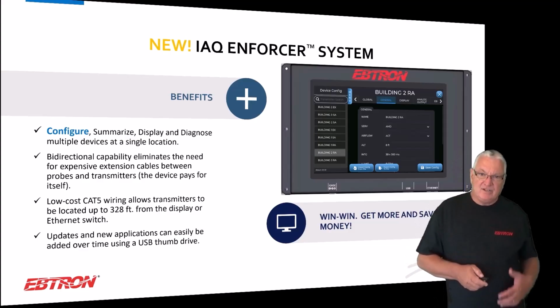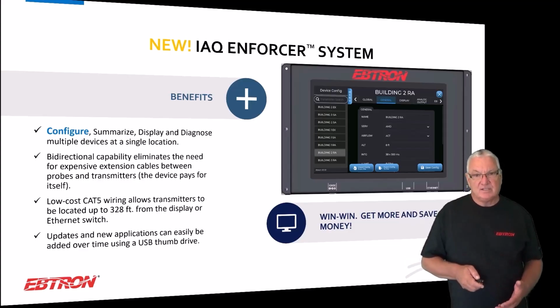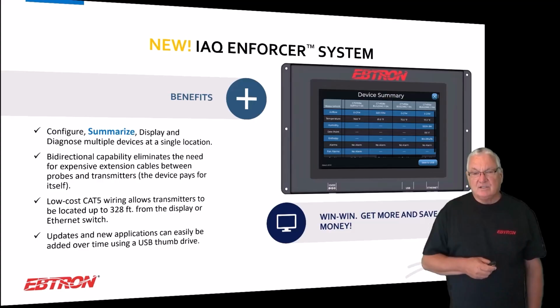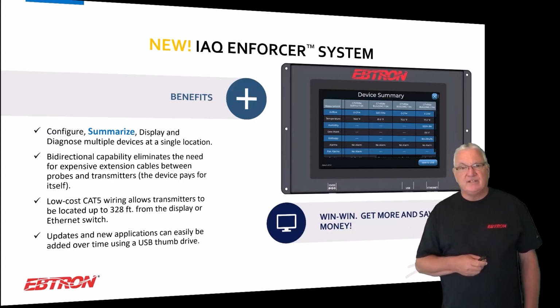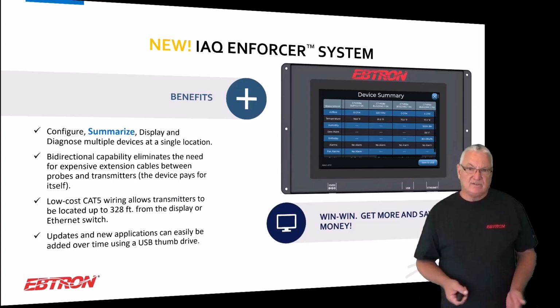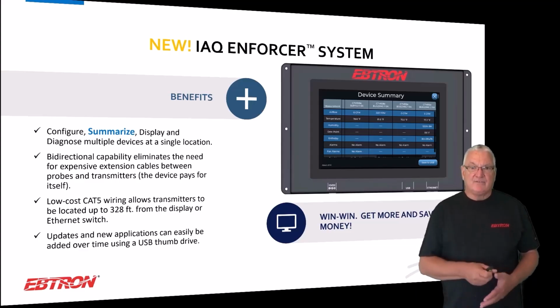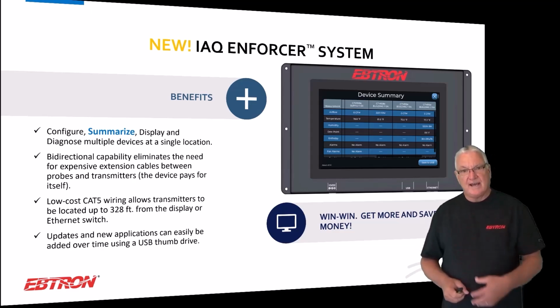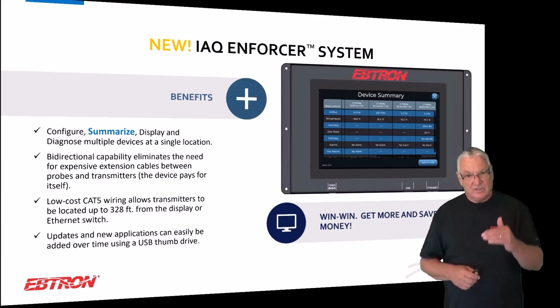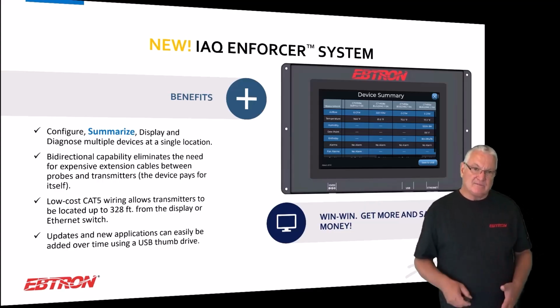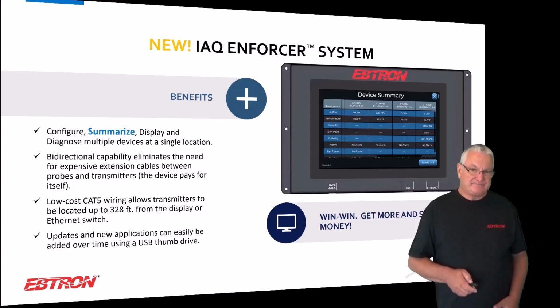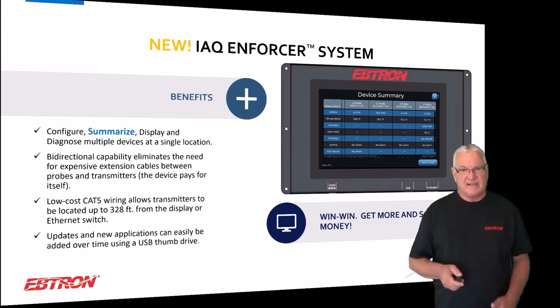So one of the applications is configure, because you have to be able to configure the device. Another one is just a summary. It shows you everything that's connected, and a device may have, like the Gold Series transmitters with the humidity sensor, up to 5 outputs that it's measuring: airflow, temperature, humidity, enthalpy and dew point. So it's going to show all that for that device, and all the devices connected. I like the summary screen quite a bit, and it's a scroll up and down type of thing, so you can see everything.